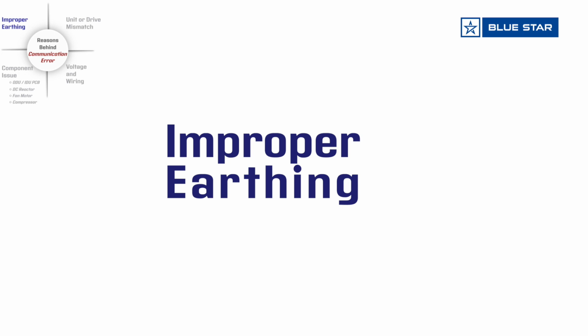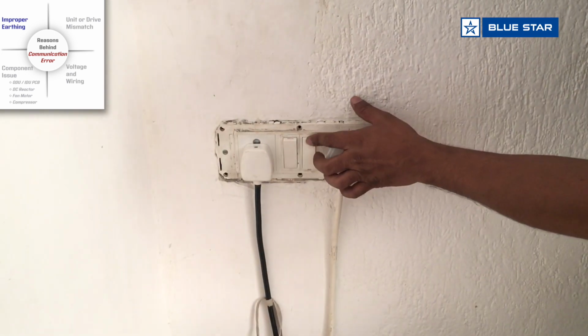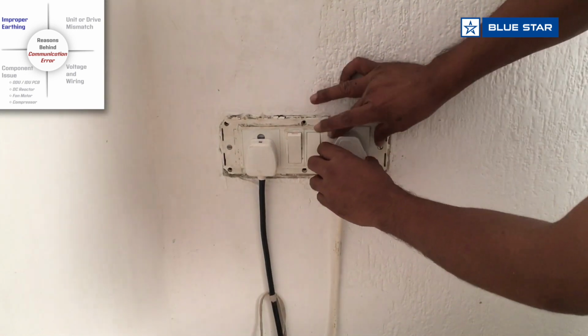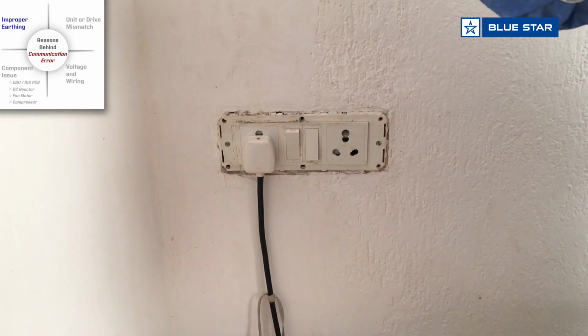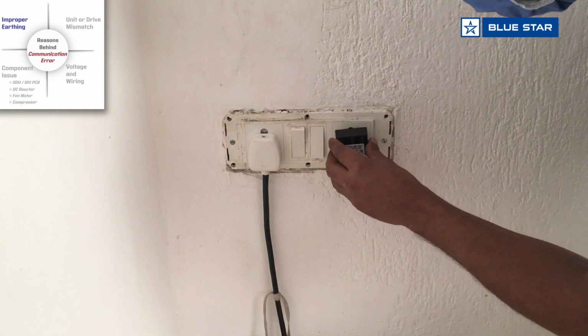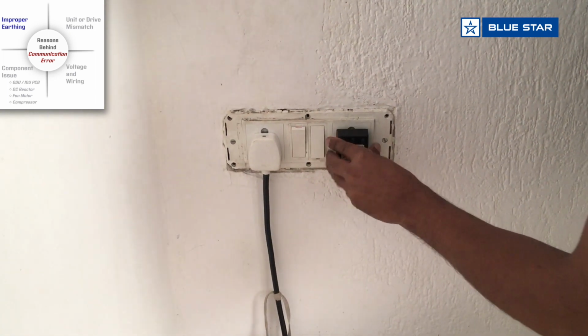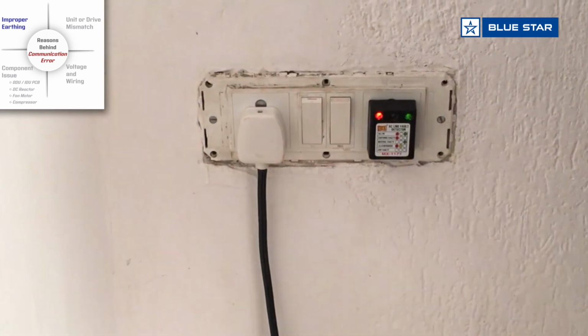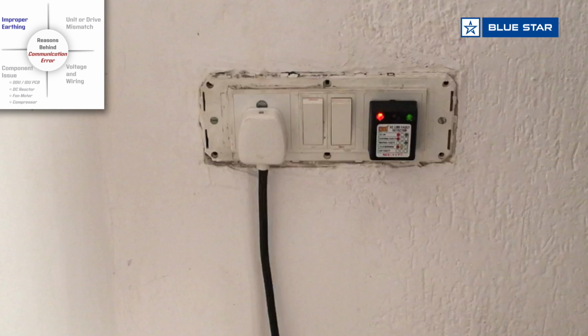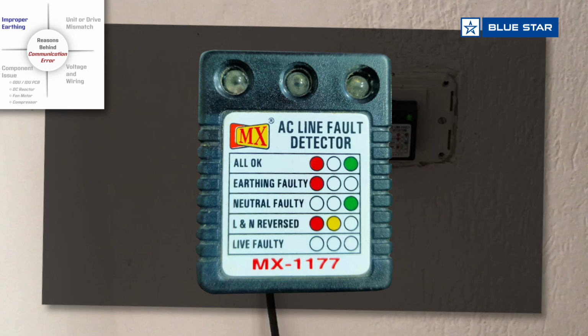Let's start by checking the input supply to the unit. Switch off the unit and take out the power plug from the power socket. Now, plug the earth line detector in the power plug and switch on the supply. In case of any issue with the input supply, like earthing is not proper, neutral is faulty, line neutral got reversed, etc., then ask the customer to get it rectified.